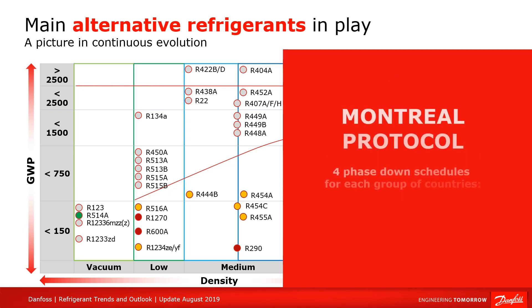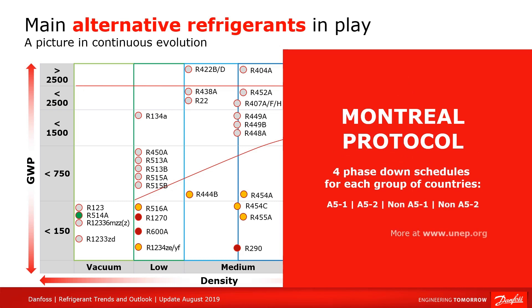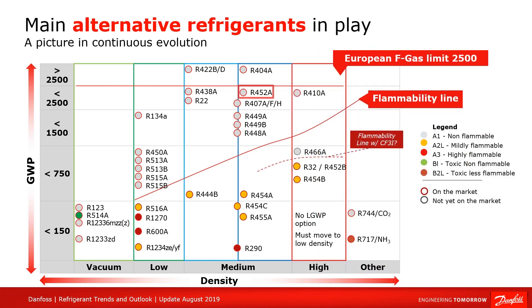In fact, many developing countries have begun using the refrigerants which are used in the developed countries. R452A is targeting transport and low-temperature refrigerants. R448A and R449A are based on HFOs and are used in low- and medium-temperature refrigerants. They have an even lower GWP. This also means that R407A and R407F will probably be temporary solutions because of their higher GWP level, especially in countries with substantial taxes on high GWP refrigerants. Many other refrigerants are still not on the market, but they are being investigated and can potentially be in play, especially because of low GWP values. Good examples are R454C and R455A blends.